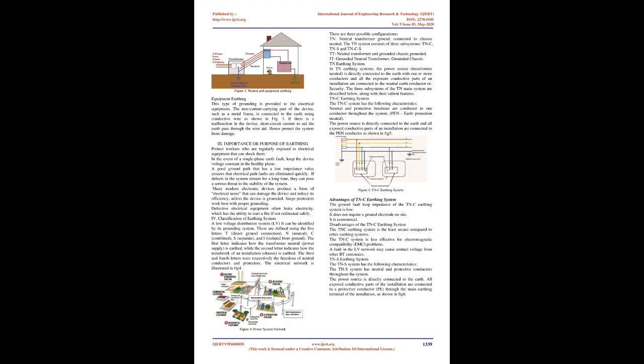Protect workers who are regularly exposed to electrical equipment that can shock them. In the event of a single-phase earth fault, keep the device voltage constant in the healthy phase. A good ground path that has a low impedance value ensures that electrical path faults are eliminated quickly. If defects in the system remain for a long time, they can pose a serious threat to the stability of the system.